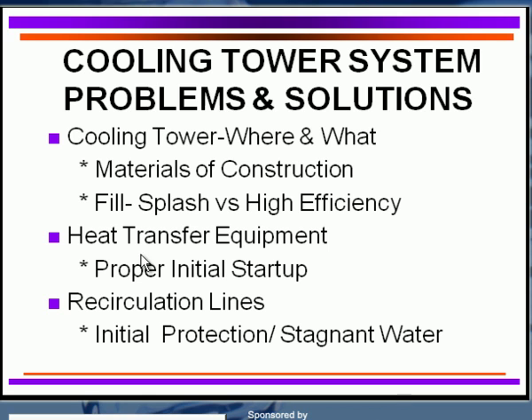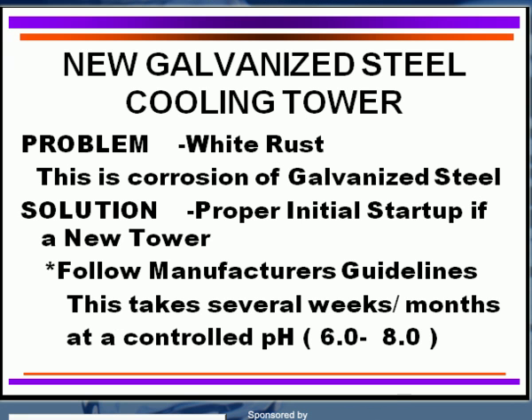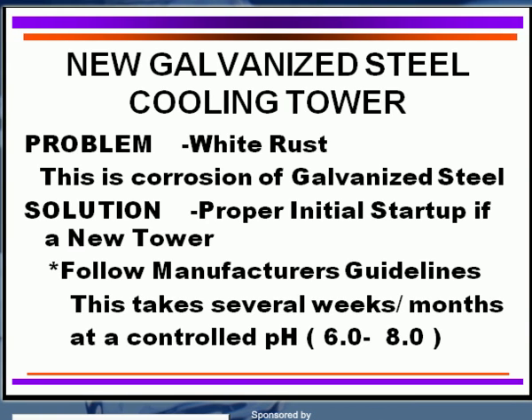Starting with cooling towers, one of the most common areas is a new galvanized steel cooling tower. One of the problems that occurs is white rust — this is corrosion of galvanized steel. We call it white rust because it's white in color, as contrasted to the red rust of mild steel.